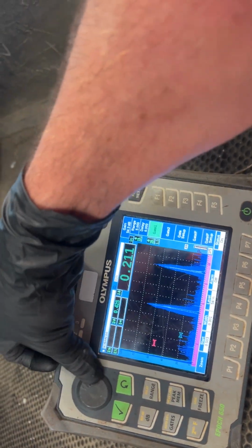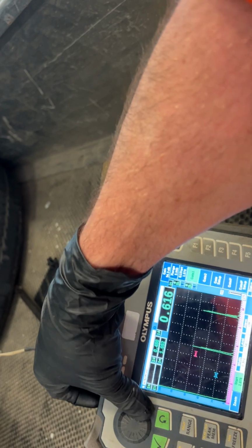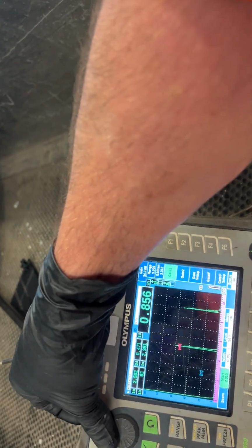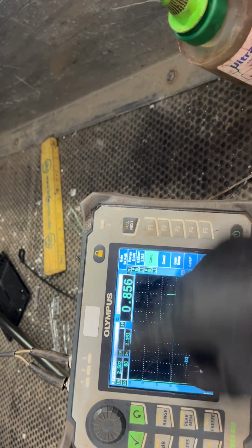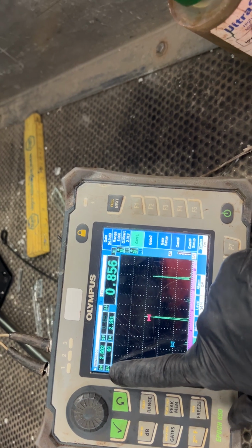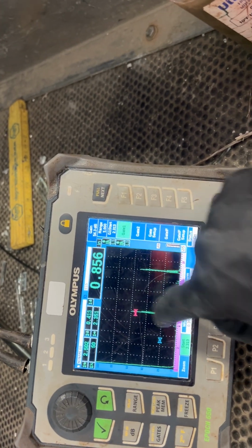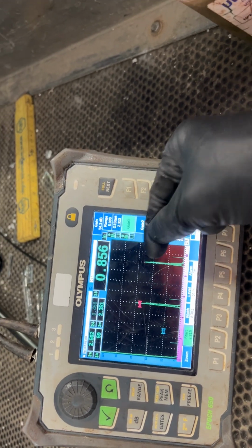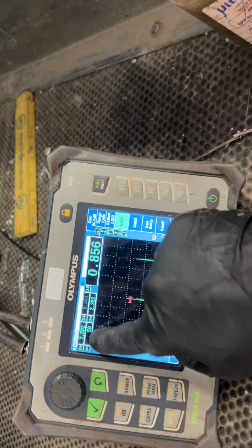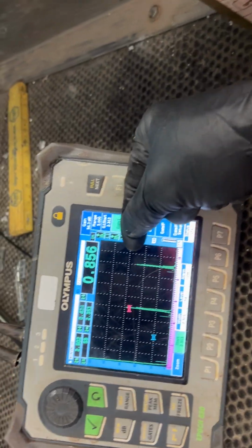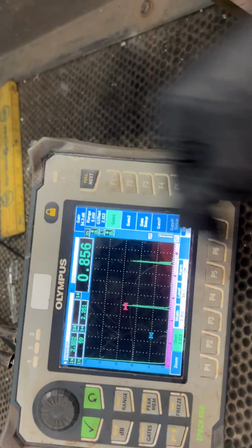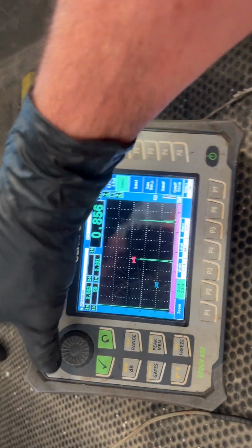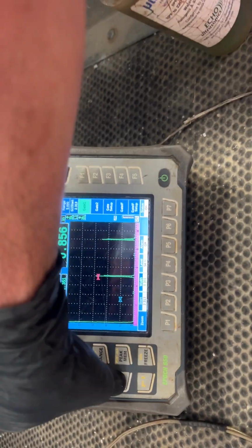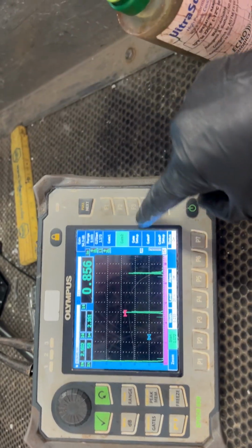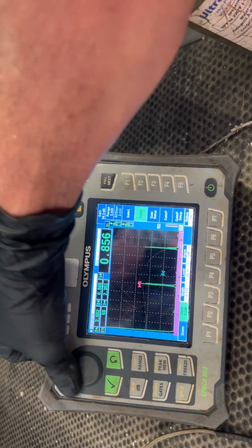Gate 1. We're going to start it. Oh, we can turn that peak memory off now. Gate 1, we're going to start it here. That should be 2 inches. I don't have my depth for number 2, so I'm going to get rid of number 1. % screen height just tells you how high this signal is in these iterations. 20, 40, 60%. Now it's 59 because it's separating the coupling. 80, 100, and above 100 it says 110. This one's also 60. Let's not think about it. Gate 1, 2, 3 to gate number 2, and we're going to move it over.